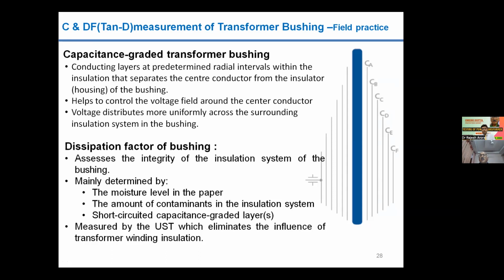In the center it is the rod, and outside, to have the grading of the insulation, various conducting foils are provided in between the insulation, so that the voltage stress is distributed evenly across the whole insulation thickness we have provided inside the bushing. So just like what I discussed earlier in the case of winding and insulation tan delta, the tan delta test is also done on the bushing, and generally we do C1 and C2.